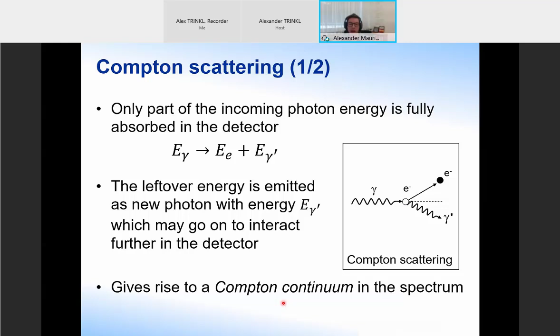This is actually not a single energy, it's rather a range of energies with slightly different probabilities depending on the energy. And that's controlled by these equations here, which I will show you for your interest, but I will not go through or derive them. What's important to note is that the energy given over to the electron, which then will be absorbed in the detector material, has a maximum. The maximum happens when the scattering angle here is equal to 180 degrees. And this is the maximum energy, and we will see the so-called Compton edge corresponding to this energy in our spectrum from a given incoming photon with a certain energy. So we will see again in a few slides how that looks.